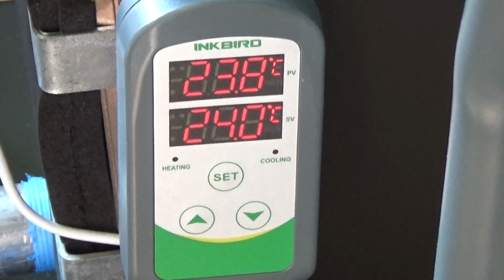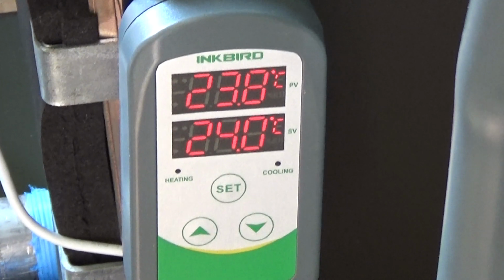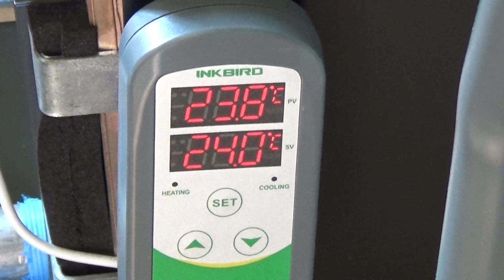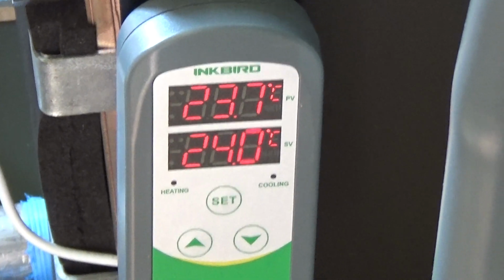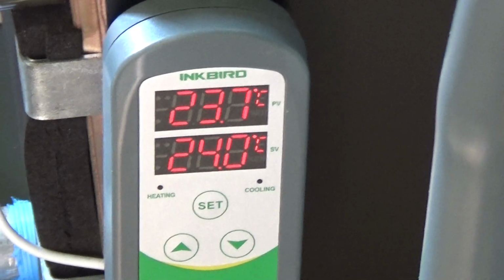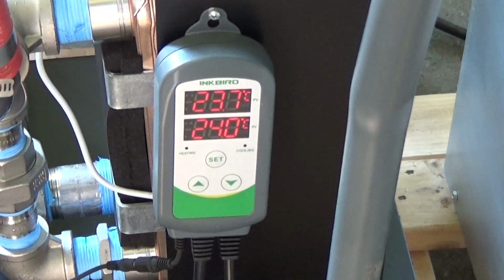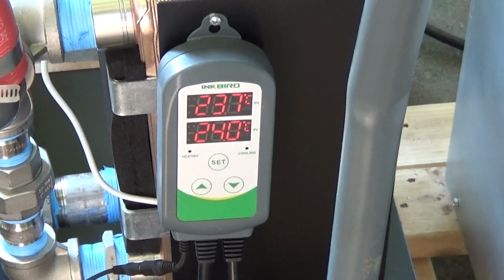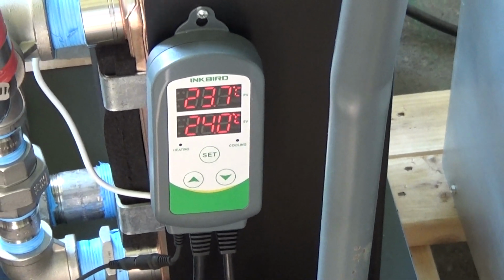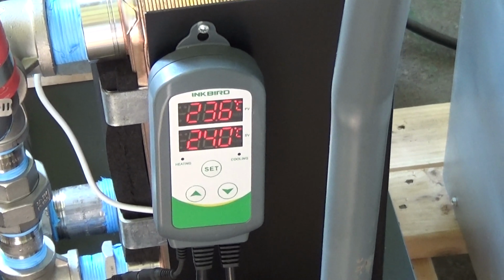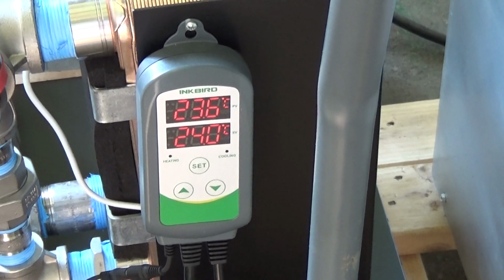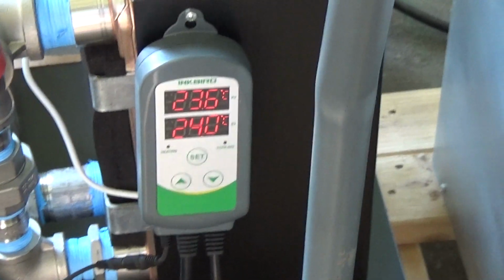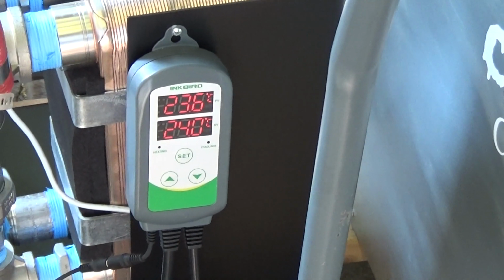You're going to get some residual cooling. You can see it dips below 0.2 of a degree, and it's going to stabilize, and now it's going to start creeping, there you go, another tenth. Now it's going to start creeping back up. We don't have much load here, maybe 100 gallons of fluid or so. In the real world, you won't get much creep past that point. So right now the motorized ball valve is closed, and the temperature is going to start creeping back up to 24.3, and that's when the valve will open up again.